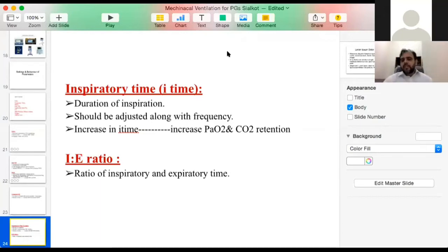If the respiratory rate is 30, then how many breaths will be delivered in 1 minute? 30 breaths. Sir, 30 breaths in 1 minute and 1 breath in 2 seconds. So what will be the distribution of inspiration and expiration? Sir, if we want to keep the ratio of inspiration to expiration 1:3, it would normally be 1:3. Sir, around 0.7 seconds and 1.3 seconds.